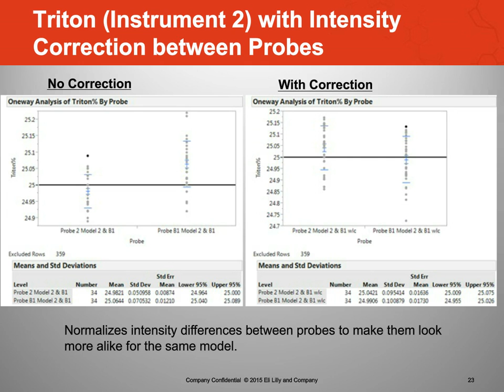The downside is we increased the variability. So our standard deviation went from 0.05, 0.07 to 0.1, practically speaking, for both of them. So the probes look much similar, but we introduced a little bit extra variability with the correction, doing intensity correction between the two probes on the same instrument. So the decision to go forward, and I think I talked about this in this next slide, was to go ahead and let's continue this intensity correction to see what it gets us long term.